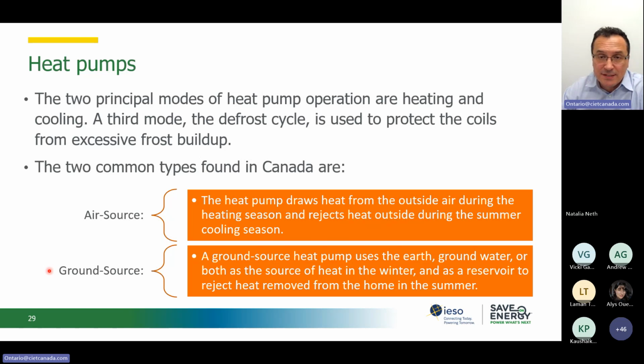And some of these installations are not operating efficiently because the problem with the ground is that we need to have a clear understanding of the capacity of the heat exchangers that are underground. So we need to have studies done. We need to see how much energy we can remove from the ground before it needs to be replenished. Because in our climate, we use a lot more energy for heating. So we remove more heat from the ground than we put back into the ground from cooling during the summer.